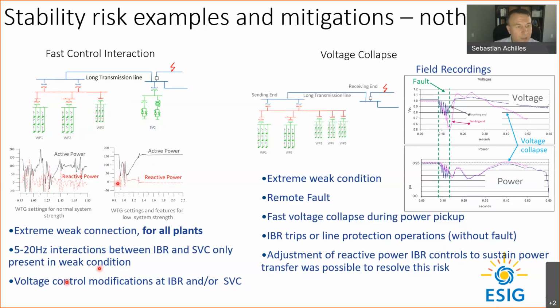This particular problem was actually solved by modifying the inverter-based resource settings - the voltage regulation. Modifying the SVC was also a feasible option at the time. This plant has been operating for many years. The problem on the right is called fast control interaction because you have two power electronic control sources or devices interacting.